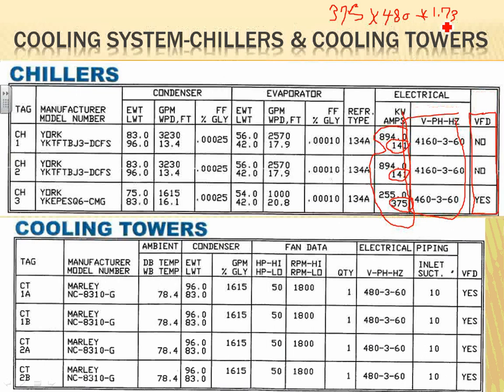That's sizing the service. When you size the feeders for it, I have an example. You take the rated load amps, and I do have two examples, guys, for you on the sheet. You just multiply by 1.25 to size the feeders.